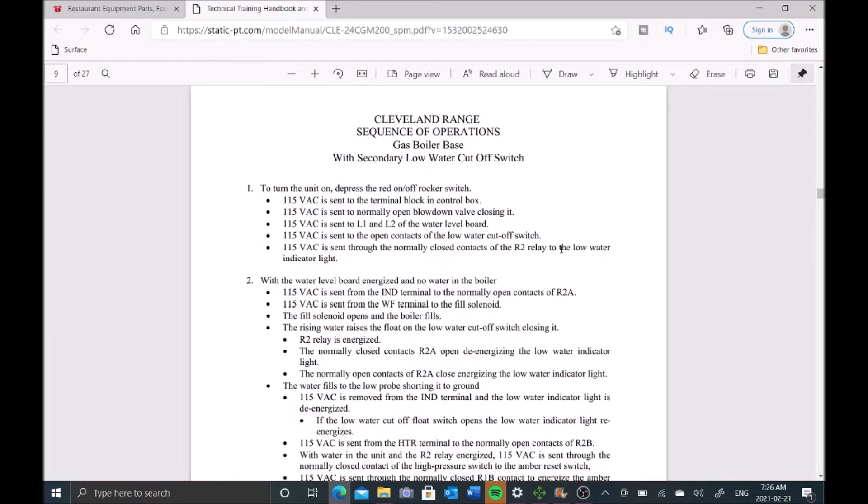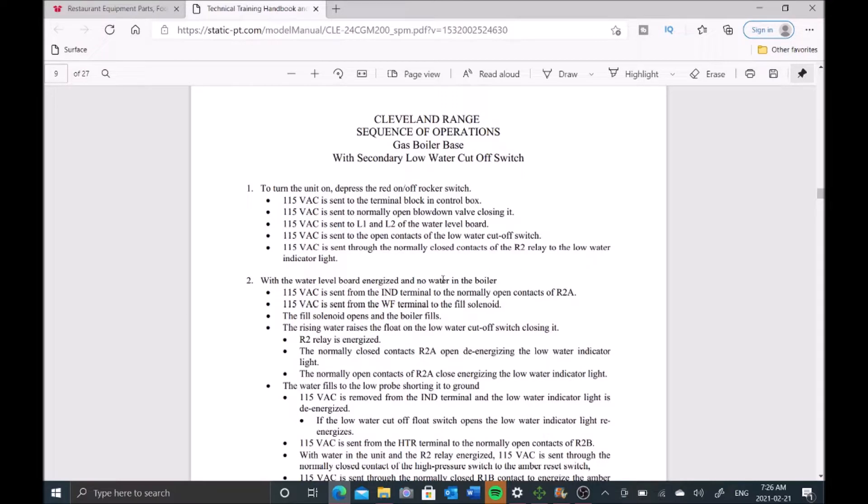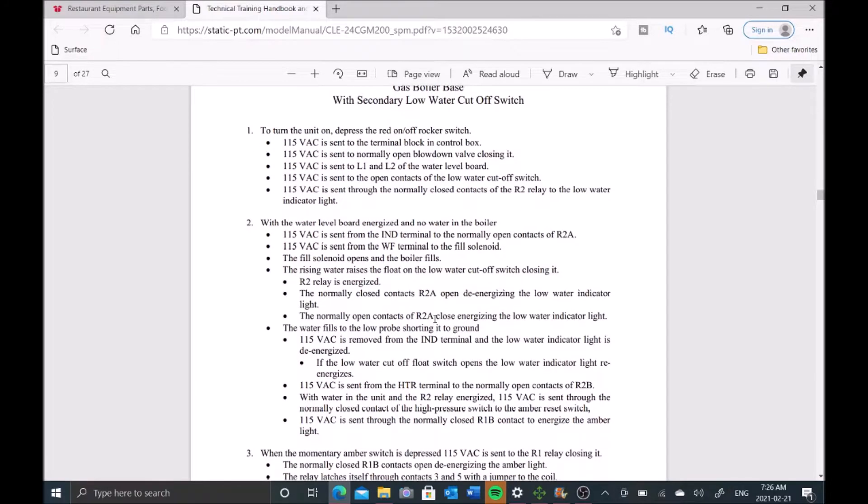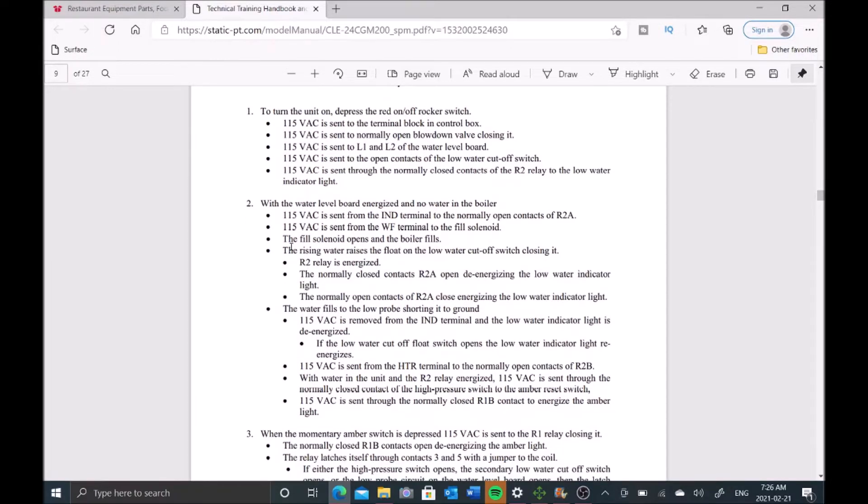Let's pull up a service manual. We have a couple hints - the low water light's on but the amber light is also on. The amber light means we can fire up the boiler so that we can get the burner going. Let's go to our sequence for filling.